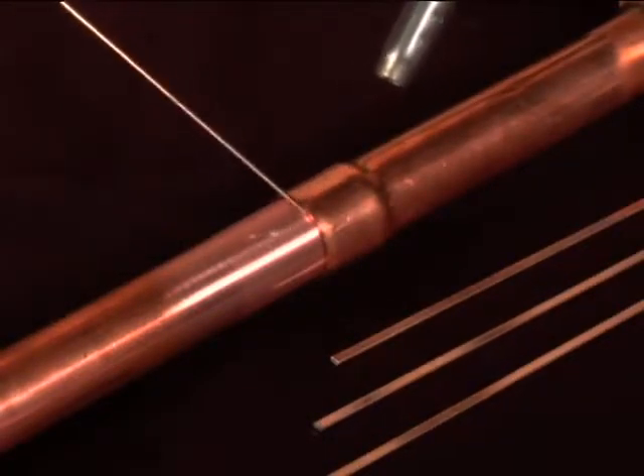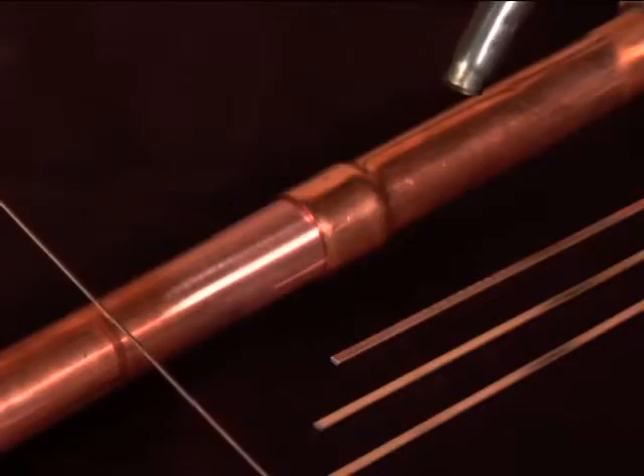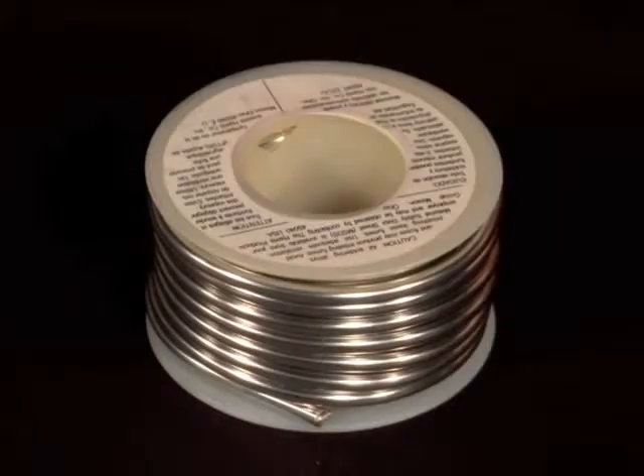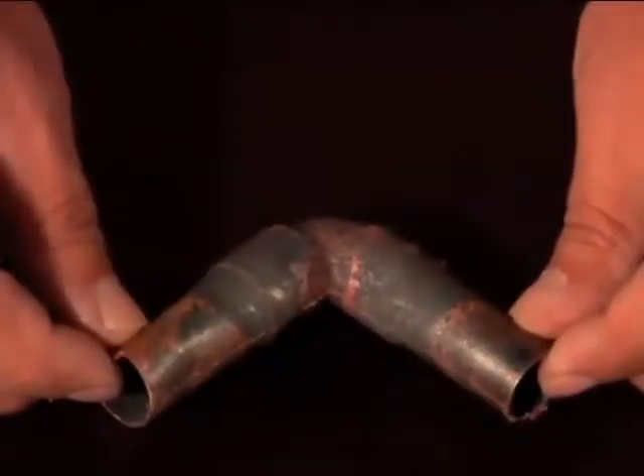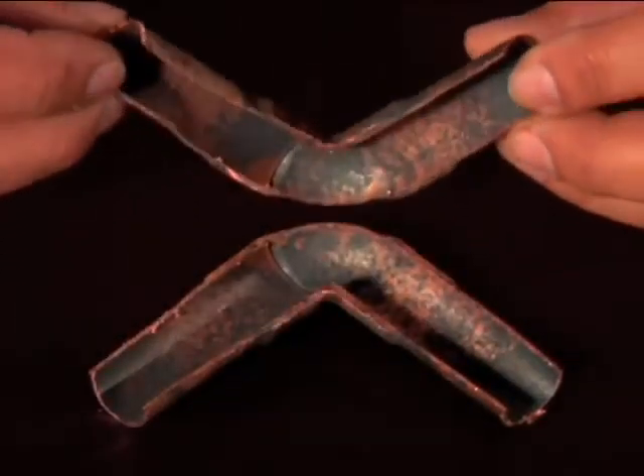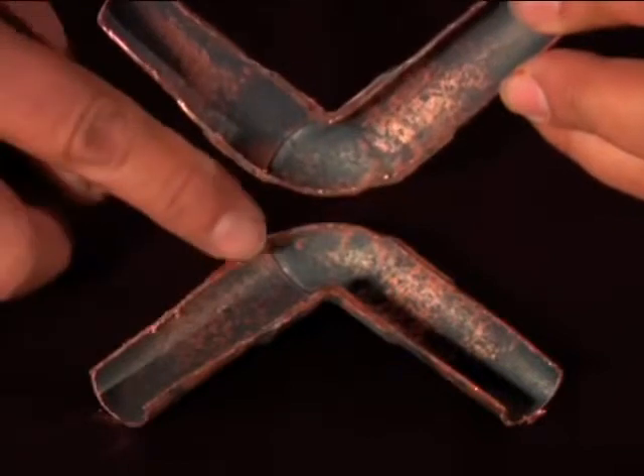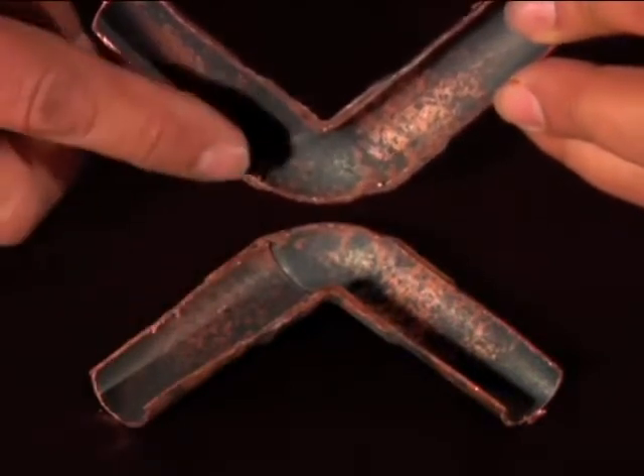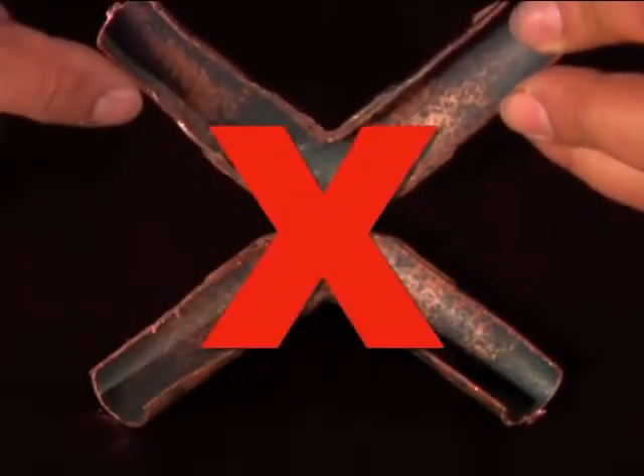The alloy must conform to the American Welding Society BCuP classification. Never use solder on a medical gas system. Keep in mind too much heat or insufficient purge or a combination of the two will result in a formation of copper oxide inside of the tube.